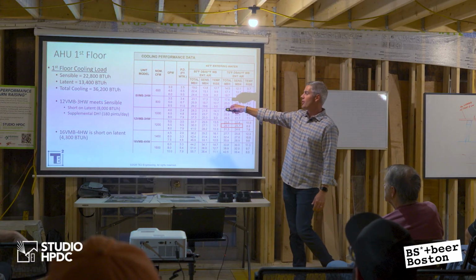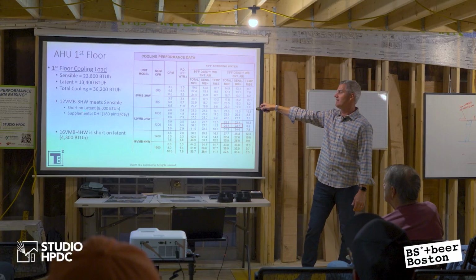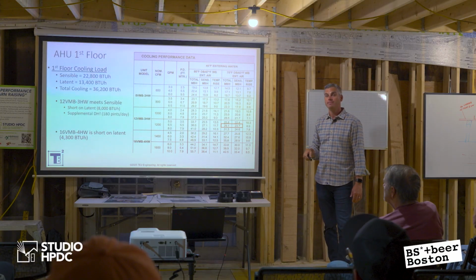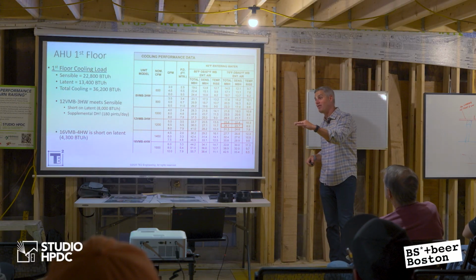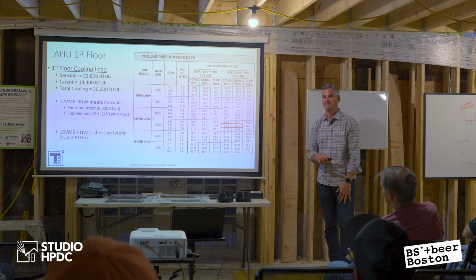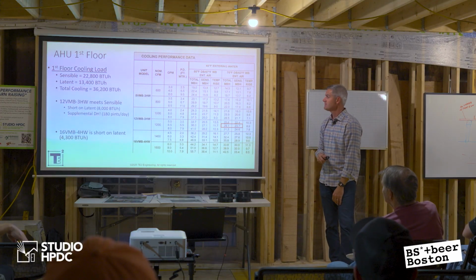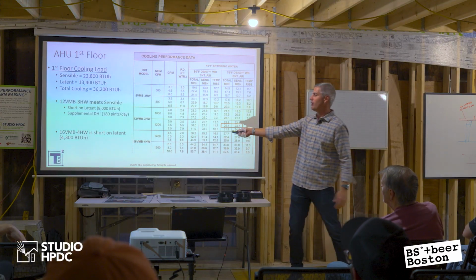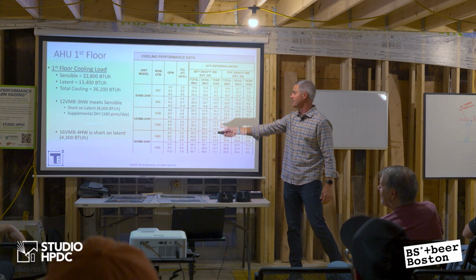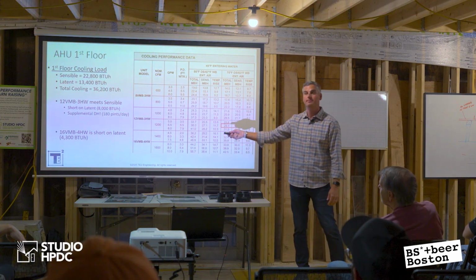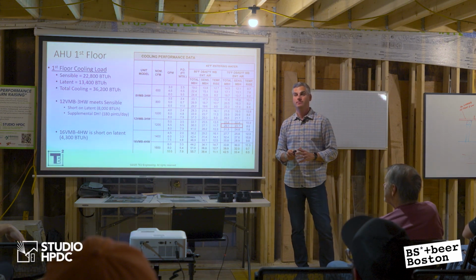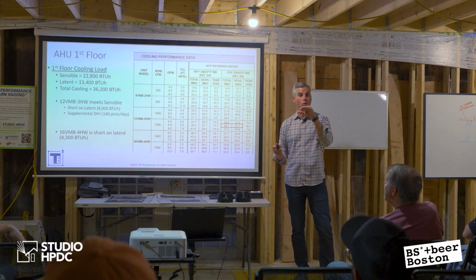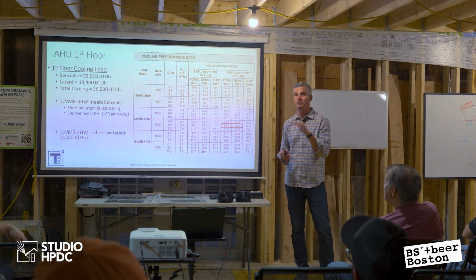But I'm a little short on my latent. The reason I'm short is because I have 55 people breathing, giving off all that water vapor. Even if I went to the next size up, I'm still going to be short. Dehumidification in this room will be needed. A supplemental dehumidifier will be needed.